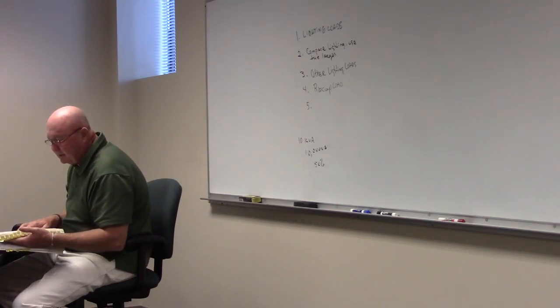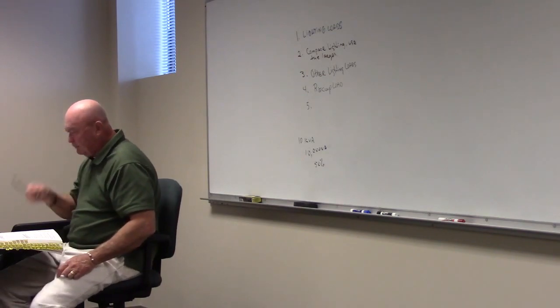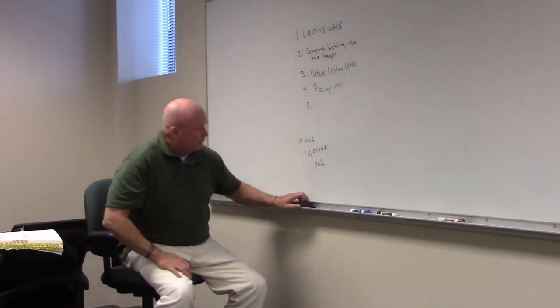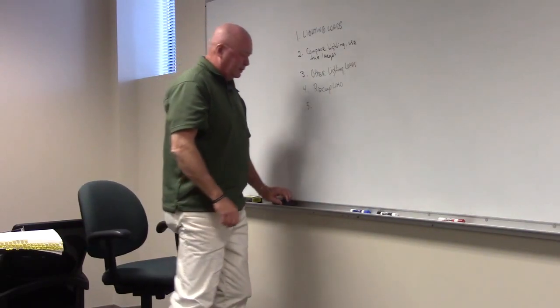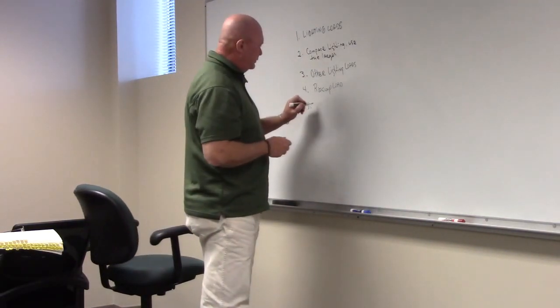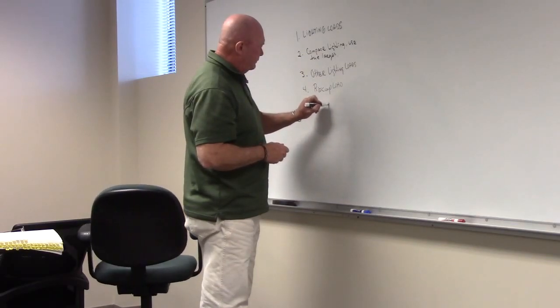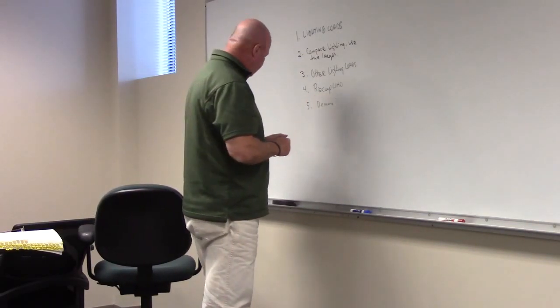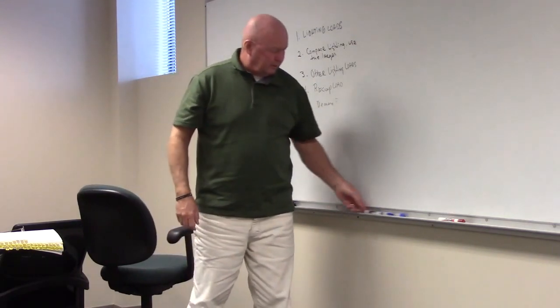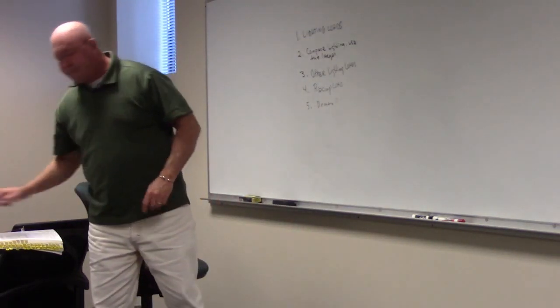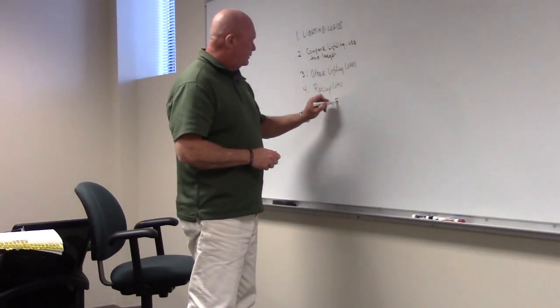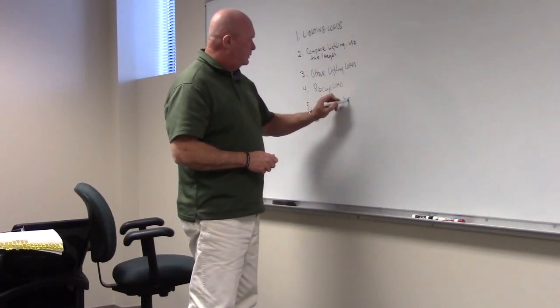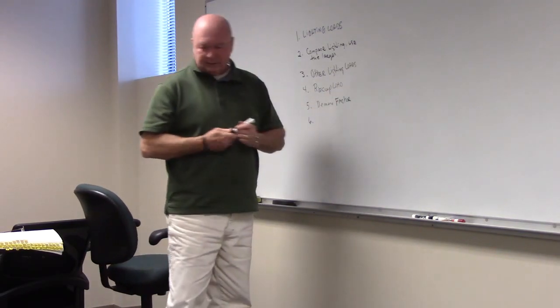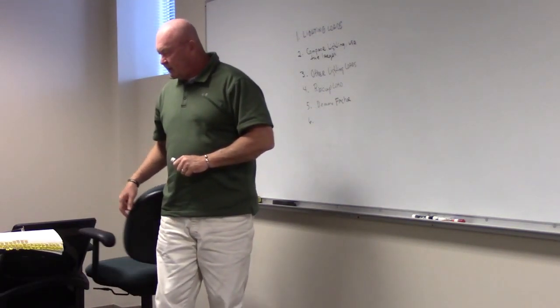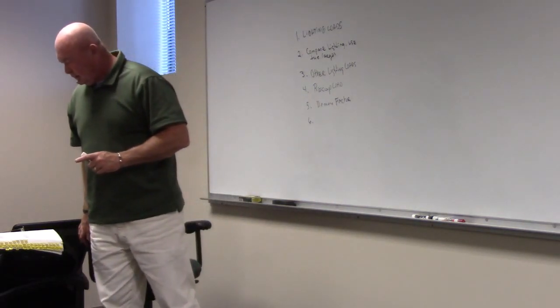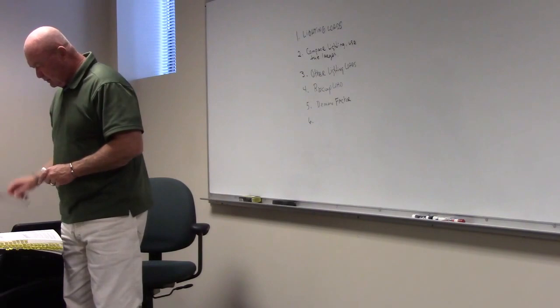Okay. All right. So we got demand factors. So step 5 would be demand factors. We have to apply them to certain situations. I picked up the wrong marker. That's number 5. Number 6, calculate all the motor loads in accordance with 220.50. Let's turn back there.